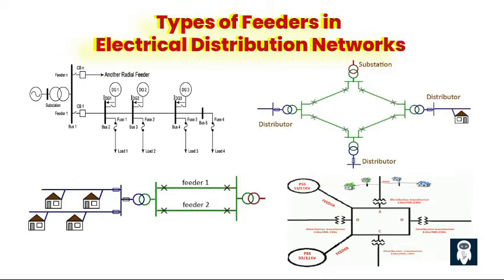Third, a parallel feeder consists of multiple feeders connected in parallel to supply power to a common set of loads. It helps distribute the electrical load across multiple paths, allowing for load sharing and redundancy. Parallel feeders are employed where power demand exceeds the capacity of a single feeder or for providing backup power options. Fourth, a loop feeder is a configuration where multiple feeders are interconnected to form a looped network, providing flexibility, reliability, and fault tolerance, reducing the impact of faults and improving reliability.